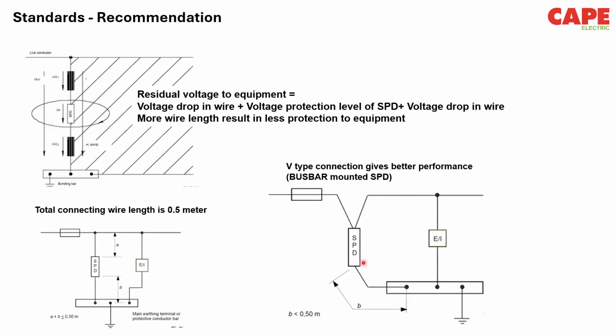And when you do a V-type connection, we'll have a little bit more margin on the downside and we can have a longer earth conductor. Okay. Or you can directly mount the SPDs to the bus bar. There are special SPDs where you can directly mount to the bus bar.